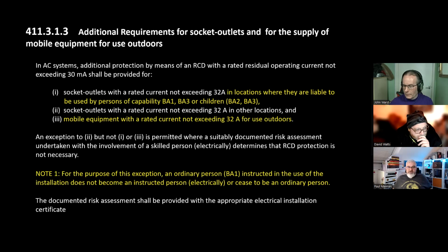There is obviously an exception to 2, which is socket outlets in locations other than your domestic areas, but you've got to have a documented risk assessment. And the documented risk assessment has got tighter and tighter because they don't want you to do it, which is fine. There is a permission to have non-RCD where there is a suitably documented risk assessment with the involvement of a skilled person. So an electrician or someone with the necessary electrical skills will determine it's not necessary. That to me is a brilliant standout regulation now, because if you have control of the utilization and the risk of it, then you shouldn't have a problem writing a risk assessment. If you don't, RCD it.